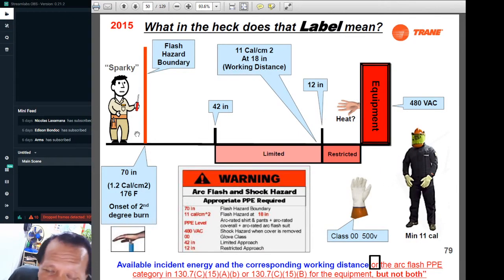And here is again an illustration of how to protect yourself. If the equipment is here at 480 volts, the restricted distance is up to here, which is 12 inches. And for somebody knowledgeable, it is up to here, 42 inches. And a non-knowledgeable person must be farther enough from the electrical equipment.